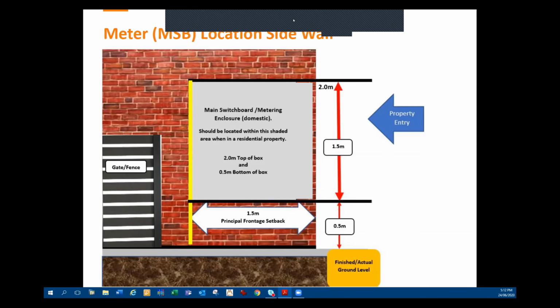There's just one more question, Martin, for you. Is there any current rules or regs for the main earth electrode to be at least 500 mil from the incoming consumer mains? Thank you. With that, there is a requirement in AS 3000. It might be one that the Office of Technical Regulator can confirm as well, but it does say in AS 3000 that there needs to be 500 mil between an earth electrode and incoming consumer mains. Okay. Cool. Excellent. I might just double check on that one anyway with Peter Lister, because I think that question was more around the water pipe rather than the consumer mains anyway.